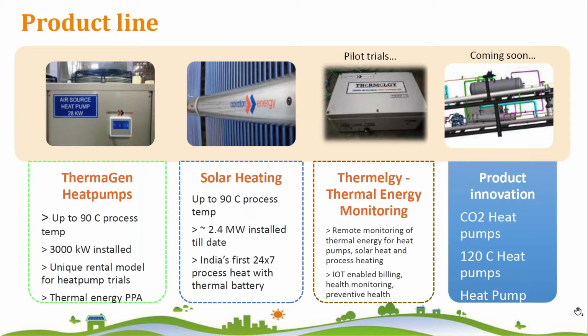We are also currently working on 3 projects. One is a CO2 based heat pump where both heating and cooling can be utilized. In this system, we can generate hot water at 90 to 95 degrees Celsius and can also generate cold water at around 5 degrees Celsius simultaneously. In the second project, a 120 degrees Celsius heat pump, which can generate hot water up to 120 degrees Celsius or steam of 2 bar. In the third project, we are working on a heat pump dryer.